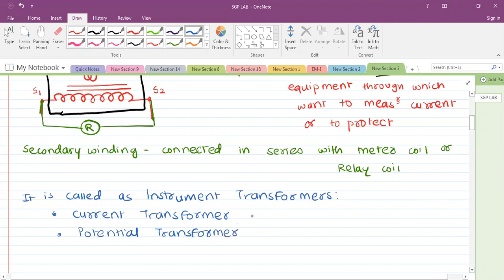The function of the current transformer is to step down the current to a safe level. Similarly, the function of the potential transformer, PT, is to step down the voltage to a safe level. To step down voltage. Fine. The connection of PT will be different. It is the potential transformer which steps down the voltage. So the primary of PT is connected in parallel with the lines. Okay, generally on the bus bar. And the secondary is connected in parallel across the relay coil or meter coil. For PT, I am saying.